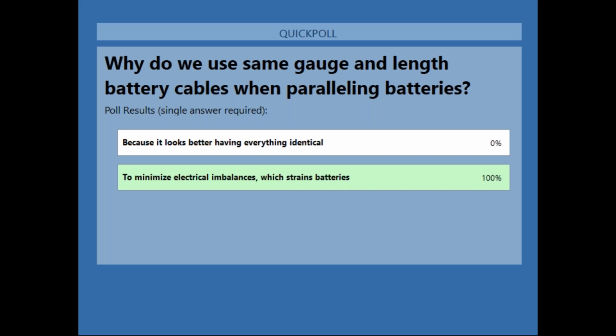The other thing you want to do is connect to the opposite corner of the batteries. I cannot stress this enough. I see people wiring off the same side of the battery all the time, and it causes an imbalance and becomes a problem. People don't believe me or realize it. But I have real data from a customer in the field this time, real numbers showing how imbalanced the batteries got and why you don't want to do this. They called us trying to figure out how to balance the batteries, and the first thing I said was just move one of your wires. It's that simple.